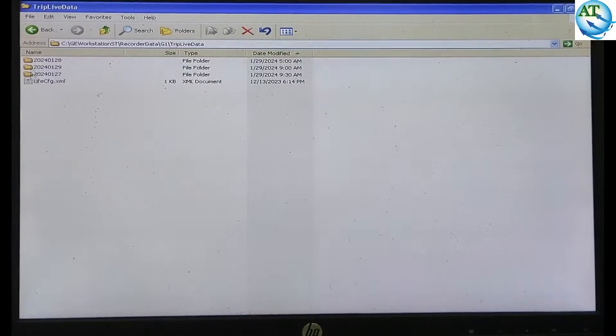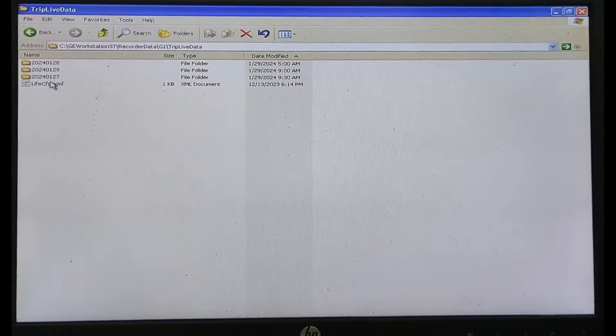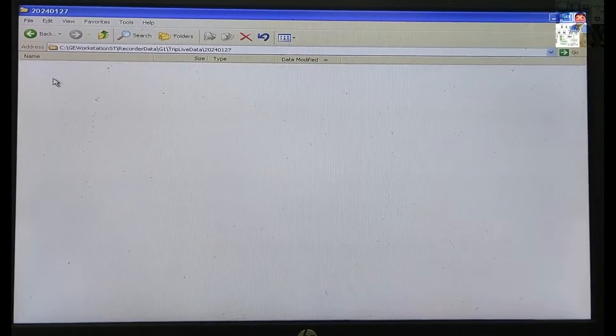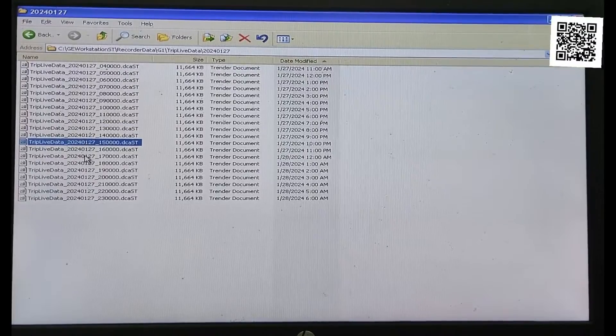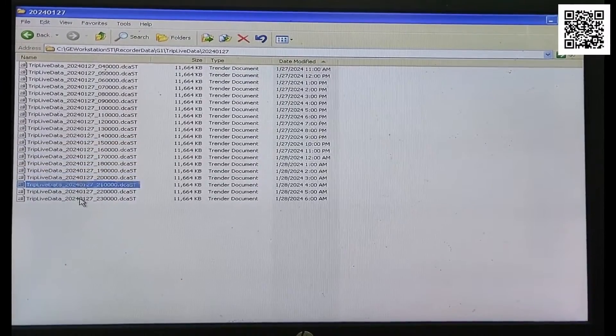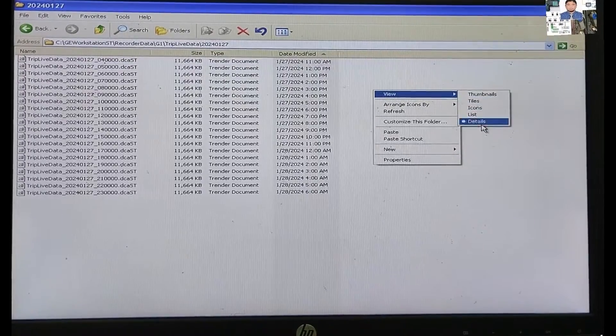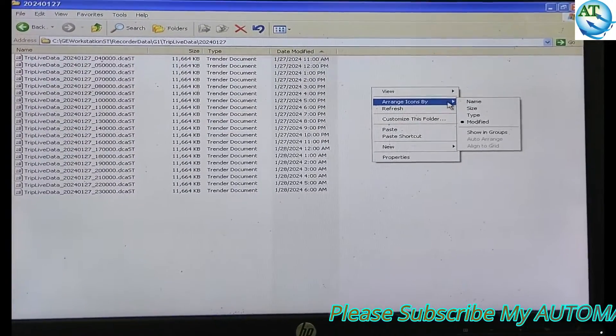If you go to TRIP Live Data, I will first show what the TRIP Live Data is. You can see that three days of data are stored — 27, 28, and 29 — three days of data stored in the TRIP Live Data. That means it is the running data. Many people don't know that in a gas turbine, some data are stored in the live data. This is the TRIP Live Data — it is the running history data, only when the turbine is running. The data is stored at one-hour intervals, and history is also stored. All the data are stored in the TRIP Live Data folder, between one hour intervals.